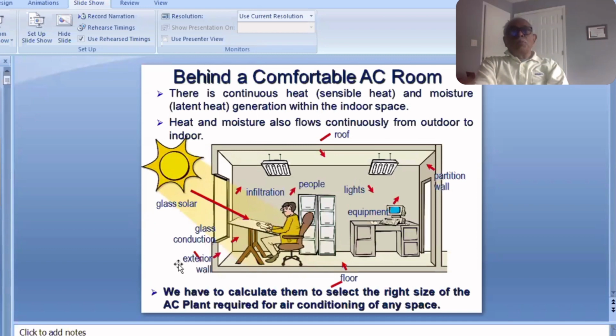There is a continuous flow of moisture and heat from outside, and there is continuous generation of sensible and latent heat within the air-conditioned space. This is seen in the picture given in this slide. The heat is coming from the sun through the glass, then through the exposed walls, then through roofs, then through floors, partition walls, etc. And people working inside are generating heat. Lights switched on inside are also generating heat, and all kinds of equipment inside are also generating heat. So there is continuous heat coming from outside, and there is continuous heat being generated from inside.